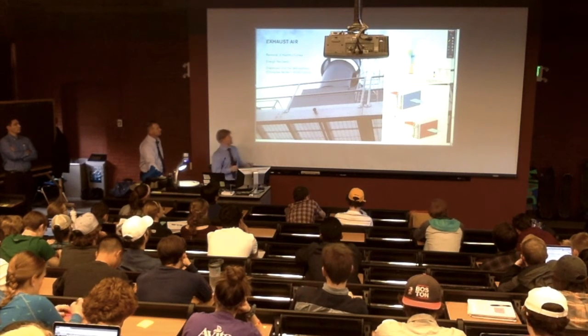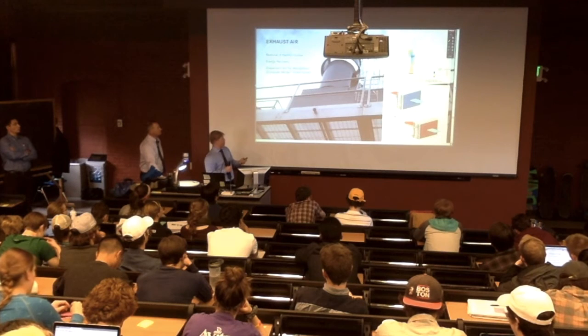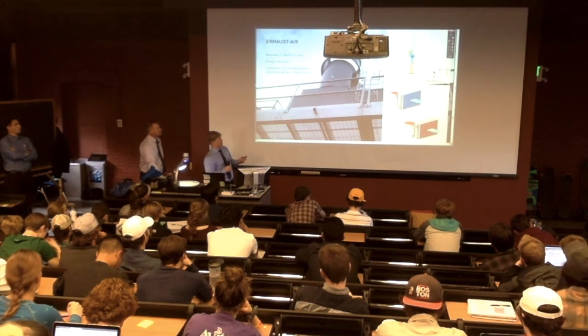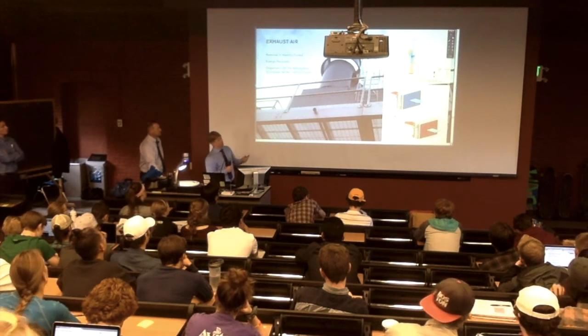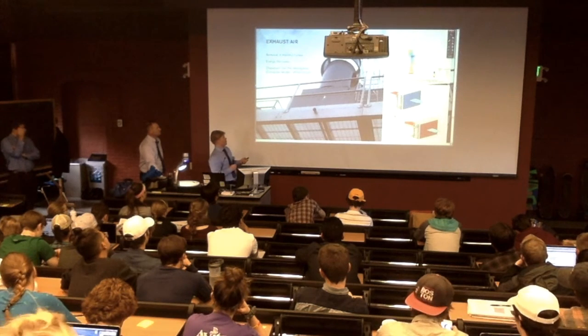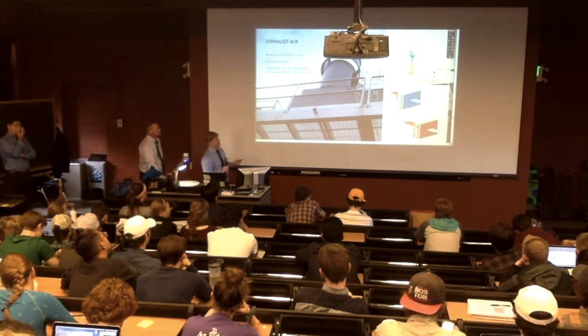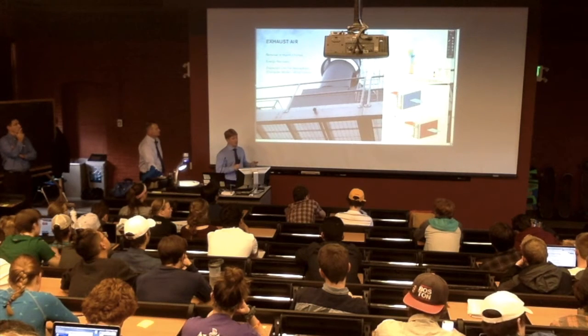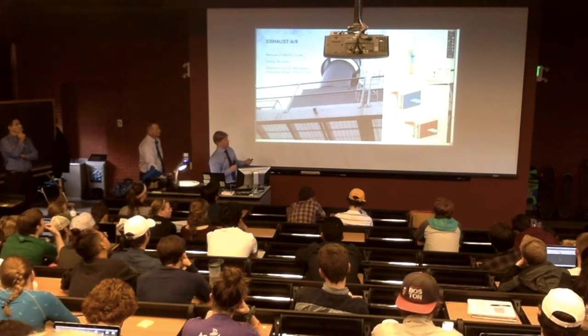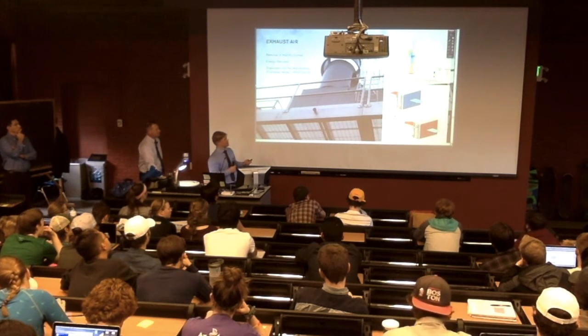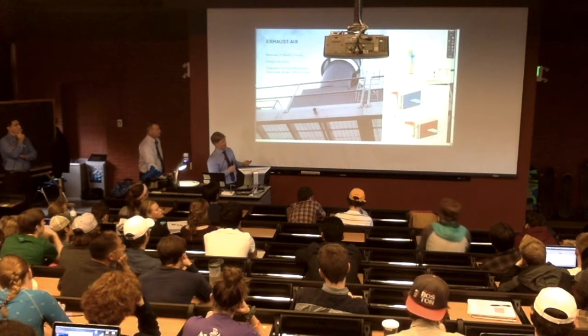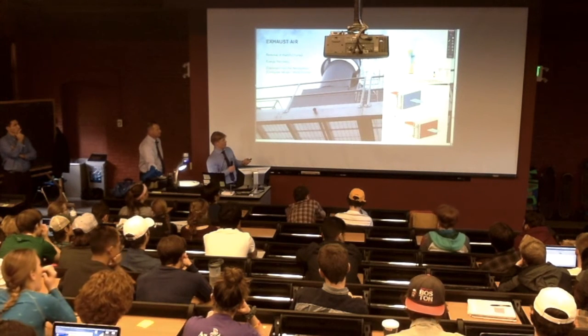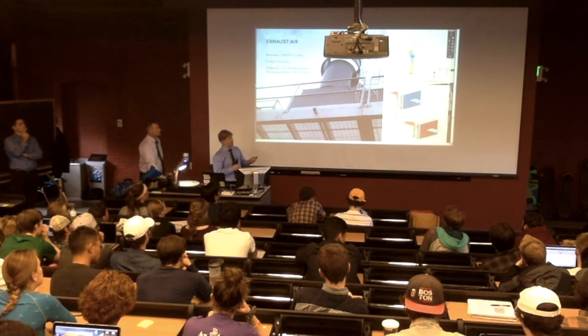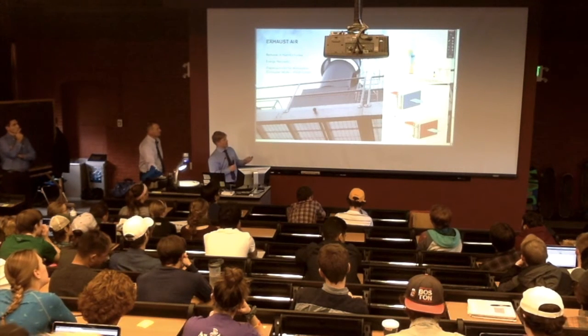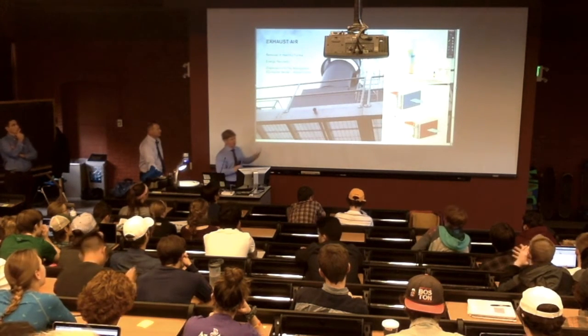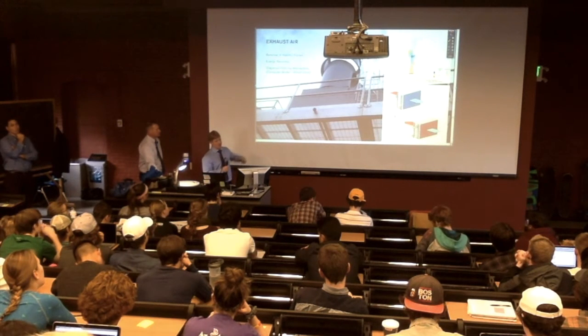The exhaust air side, this is not on that particular building, but it is an example of a type of technology that's used to disperse the exhaust air, the contaminated air from laboratories, up as high as you can. So an effective plume height is what we're looking to achieve, where it's safe and away from other occupants or air intakes. Allan was actually talking about the company we use, RWDI, they do the analysis. And this is just a chart of the prevailing southerly wind here in Burlington that we used to figure out where this exhaust was going to go after we throw it out of the building.